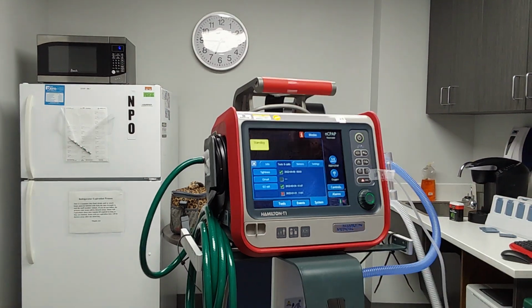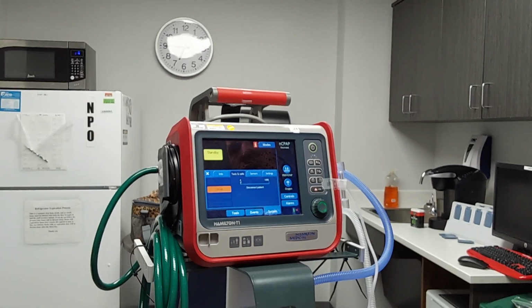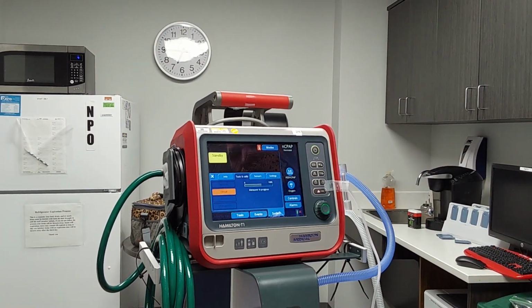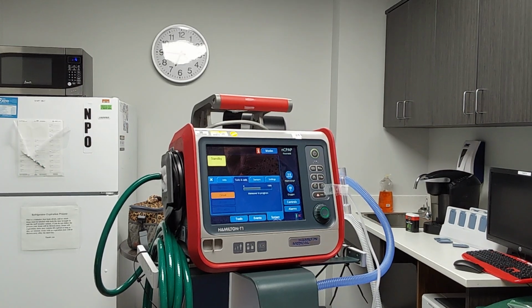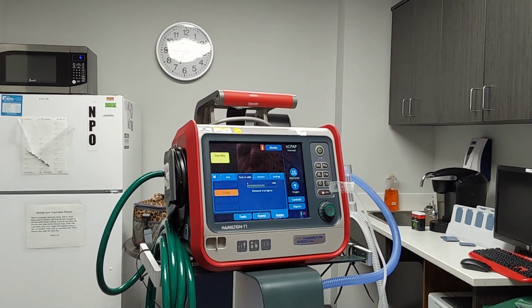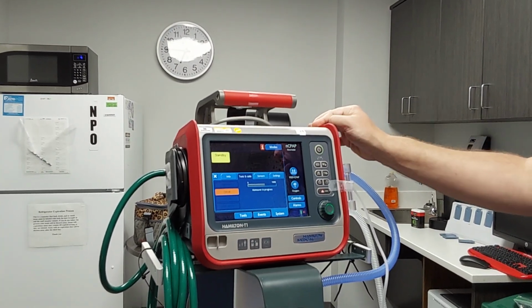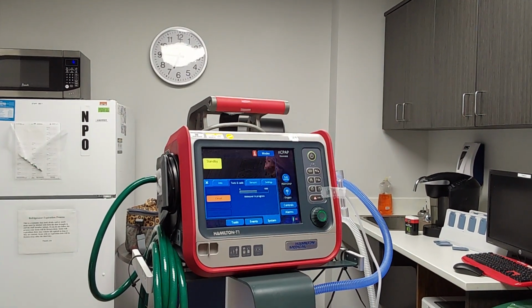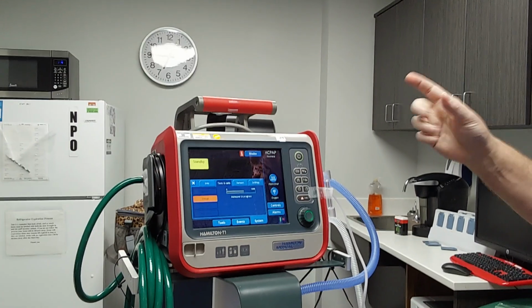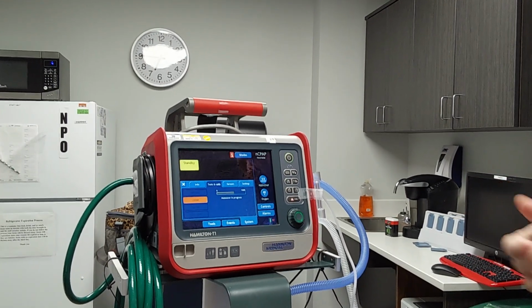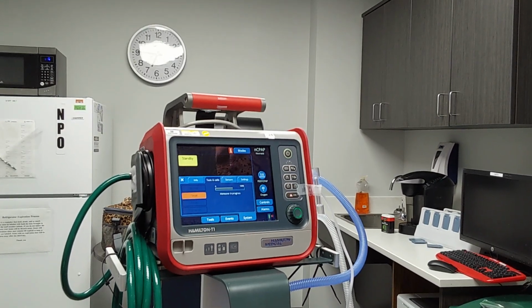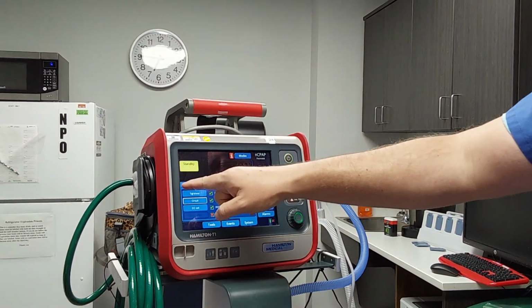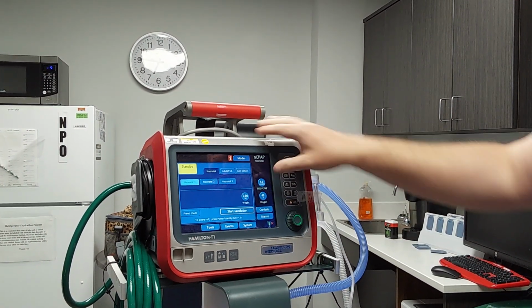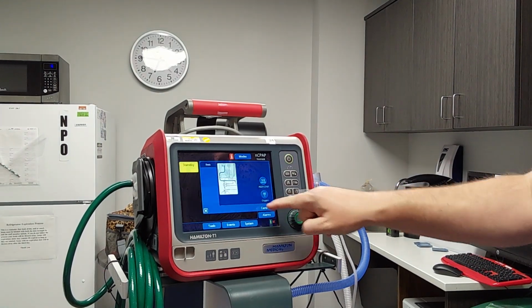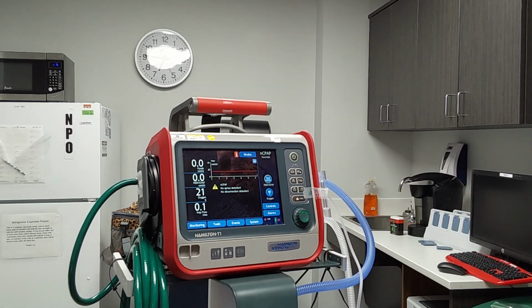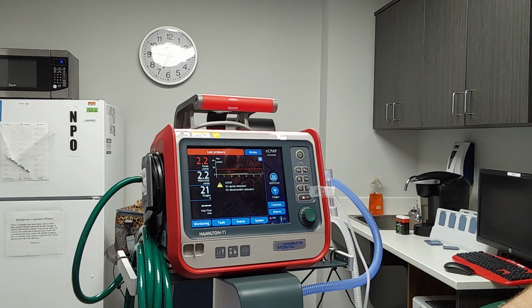The circuit has not been calibrated, so we will calibrate the circuit. Disconnect patient. Will that have to be done each time when you switch it over? Yep. Because it starts in that adult mode, so when you turn it on, the machine thinks it's adult. When you flip it over to neonatal, it thinks all of this is new, that you just set it up. Circuit's calibrated. So you're on 5 PEEP, and you have your oxygen. That's the only two settings you have. And then you get this message, no apnea detection.